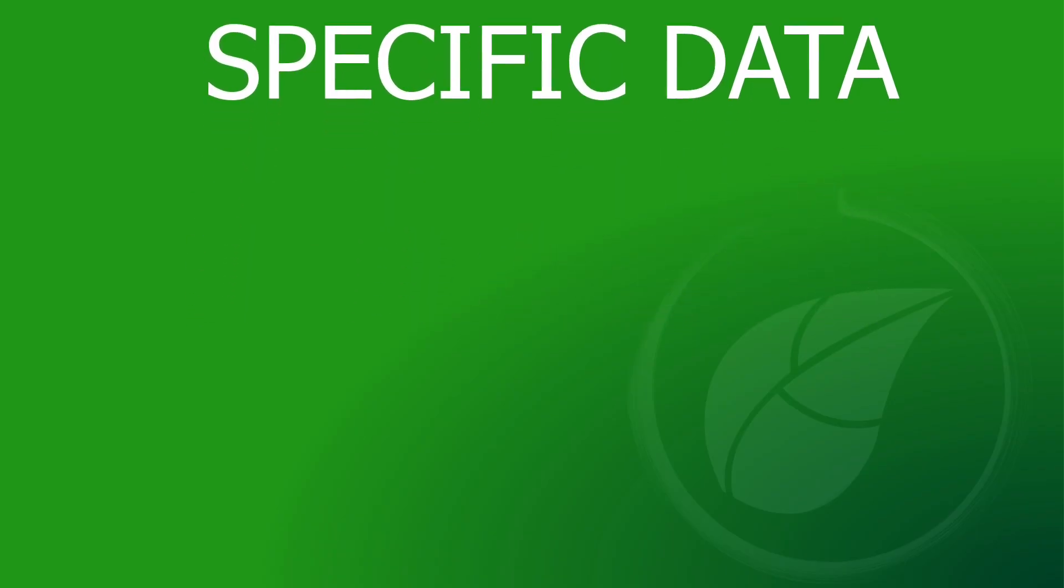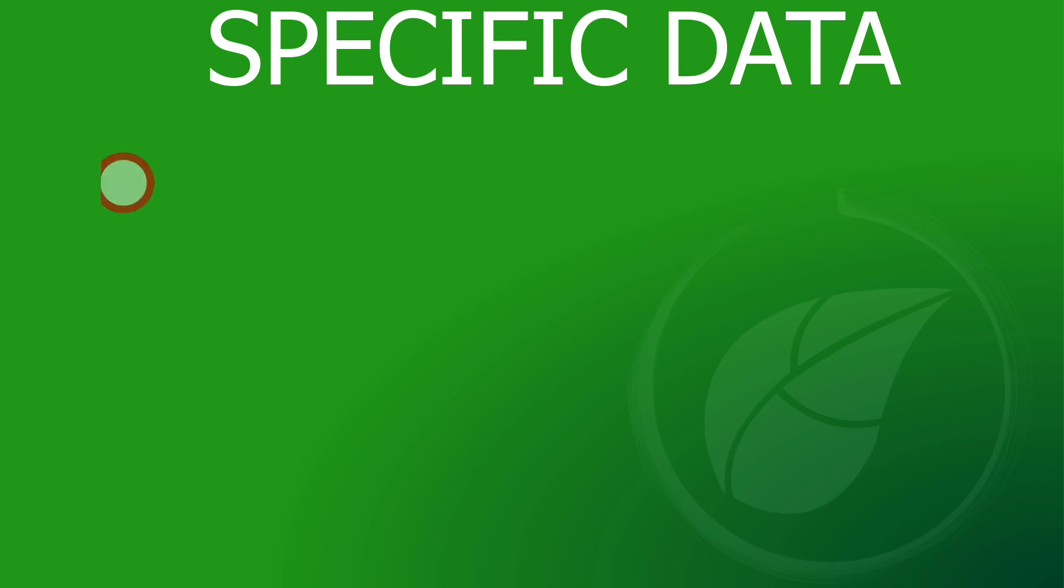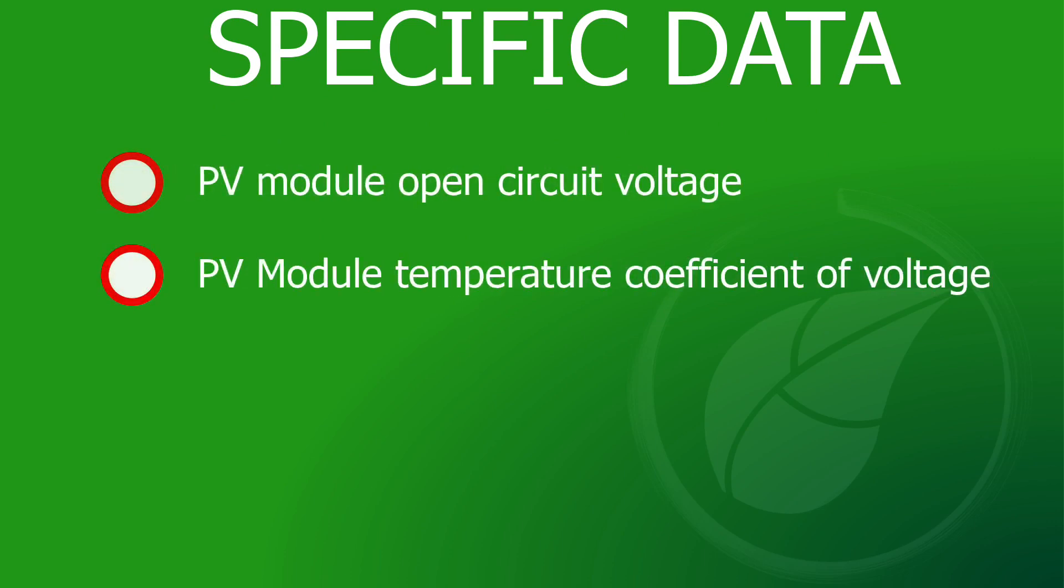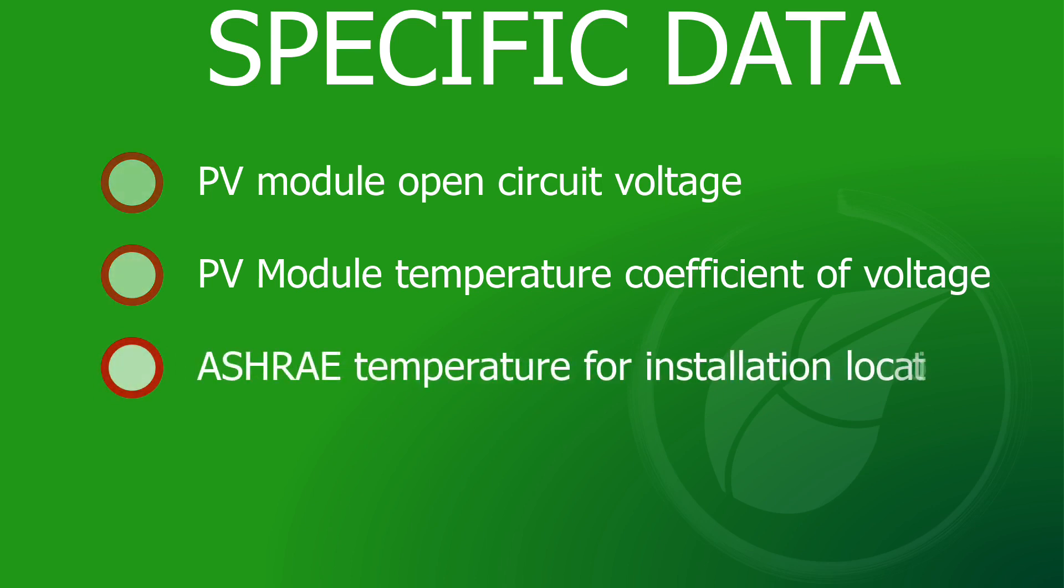There are three pieces of information we will need: PV module open circuit voltage, temperature coefficient of voltage, and ASHRAE temperature data for the installation location.